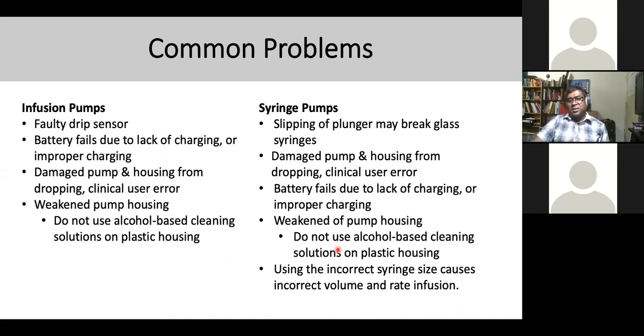Weakening of the pump housing: do not use alcohol-based, pure alcohol-based solution to clean the plastic, because the housing can easily break and change color. At the same time, most of these devices are somewhat waterproof, so you're going to destroy that particular function. Like the syringe pump, you may get slipping, and the plunger may break the glass barrel. Another is damage to the pump housing because it was dropped by the clinical user. Battery is also one of the common ones, and improper charging. The same issue applies with the material or the chemical they use to clean, which can cause the housing to not be protected very well.